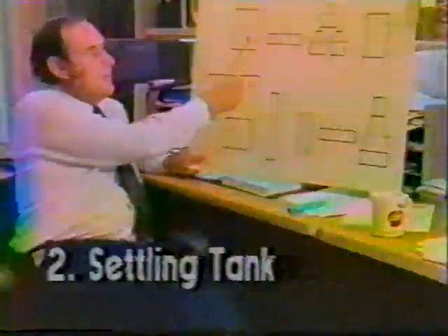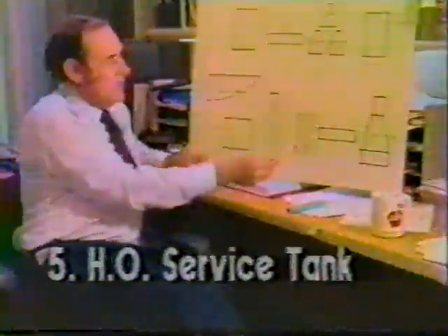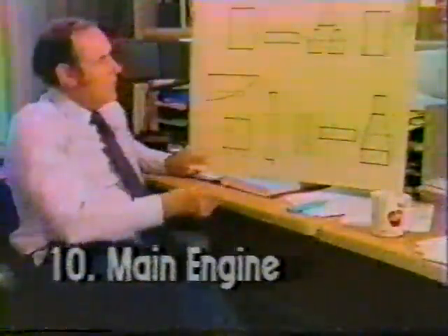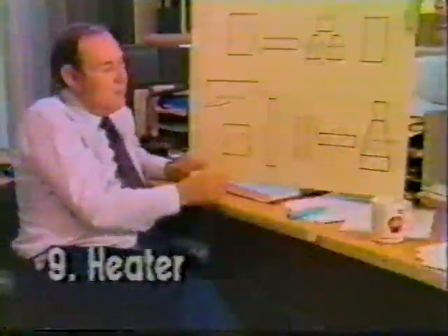We have here the bunkering storage tanks, a settling tank, heaters for the purifiers, heavy oil service tank, diesel oil service tank, a mixing tank, and supply pumps for the main engine fuel oil heater and hence to the main engine. A system that you are normally familiar with would be a storage tank, settling tank, heater configuration. All other items on the chart are unique or are relative to a slow speed, heavy fuel oil burning diesel plant.